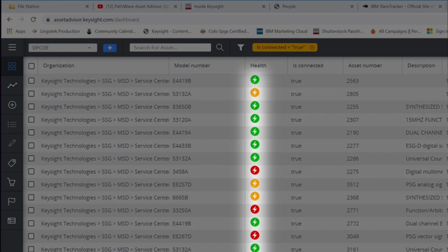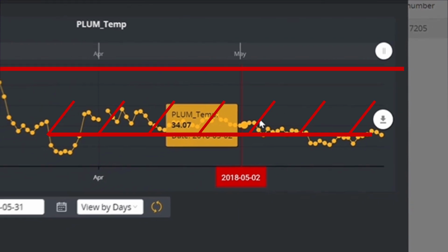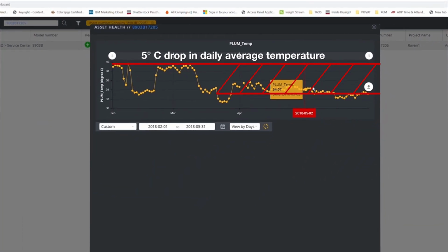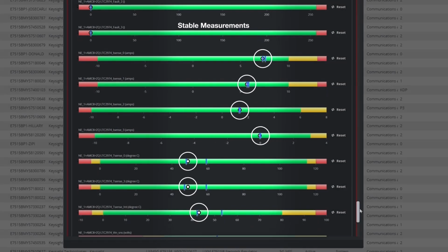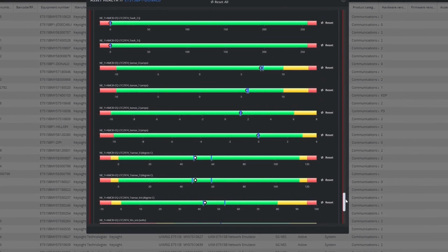Asset Advisor provides insight into the health of your instruments in real time. For this instrument, the temperature reached nearly 40 degrees Celsius. Adding ventilation permanently reduced the temperature by 5 degrees. Potential downtime avoided.